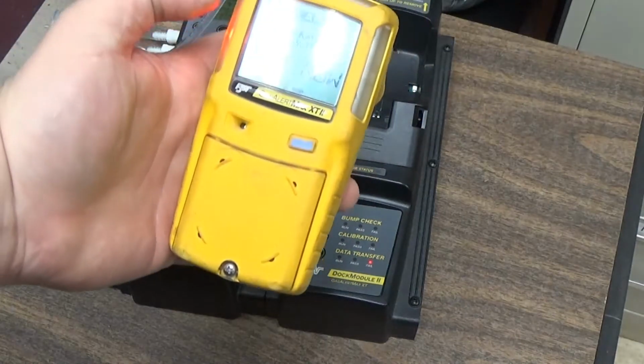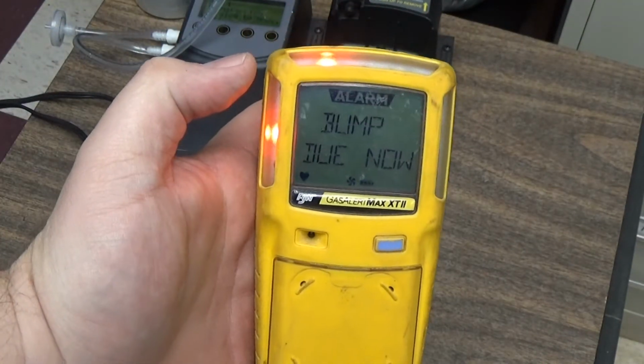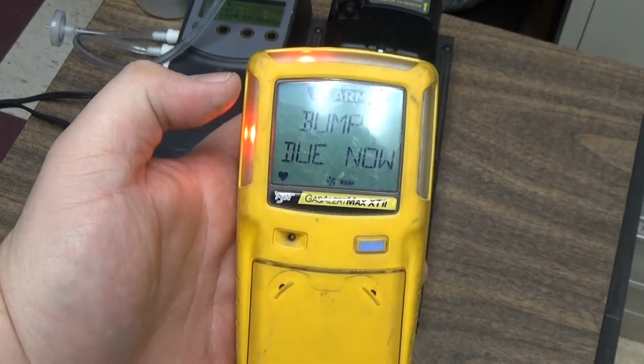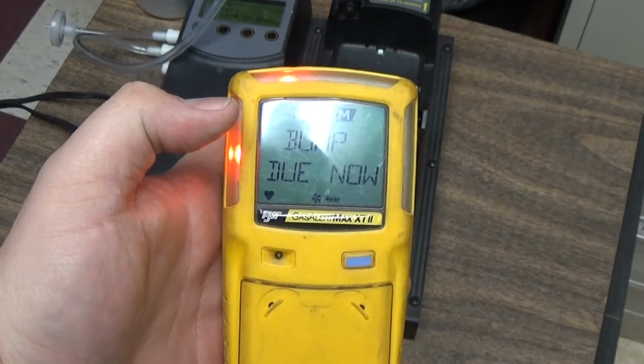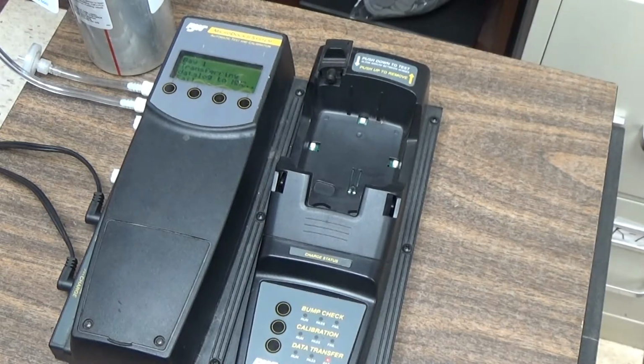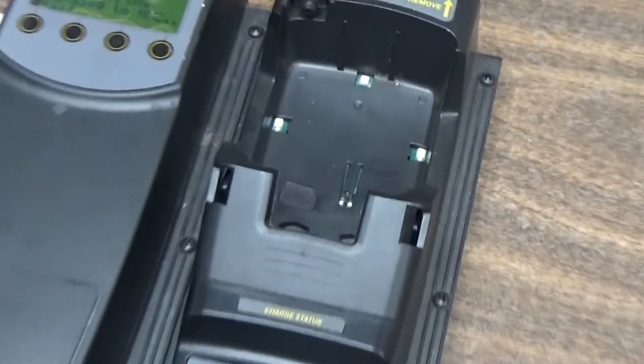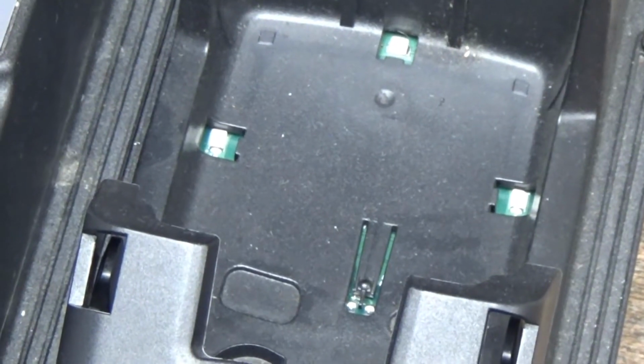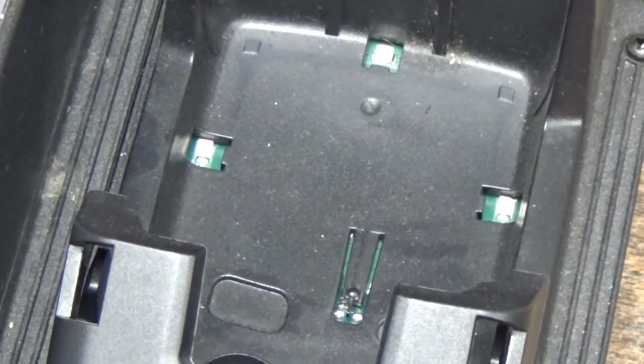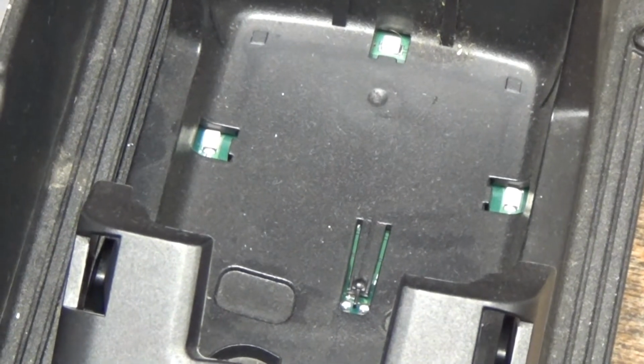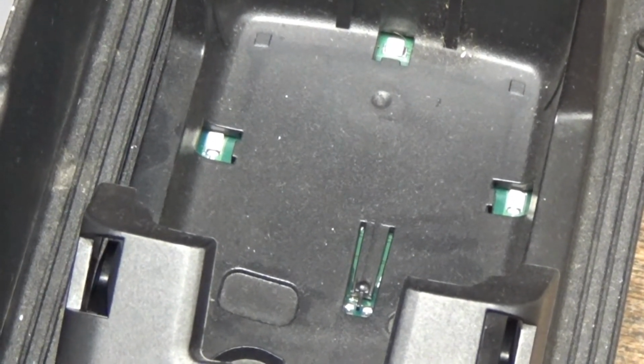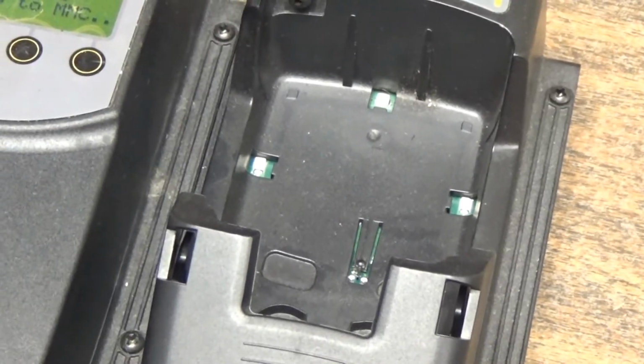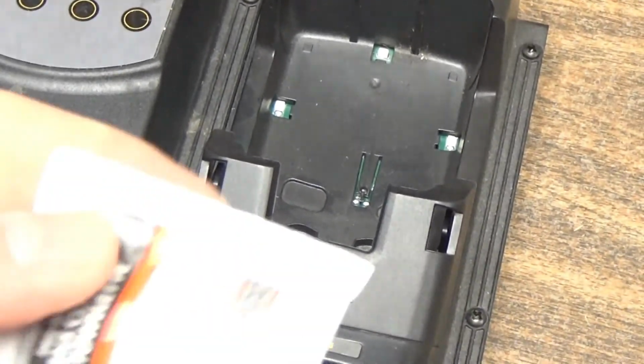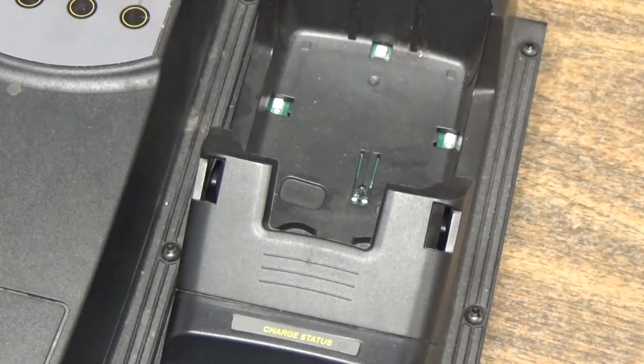If it has not passed, like this one failed, it'll still show you the bump now. You will not be able to use this meter until it has a fresh bump. One of the reasons that we found that a meter may fail on the visual test is these sensors here in the meter, or in the bump station.